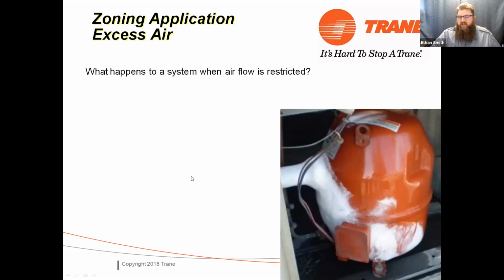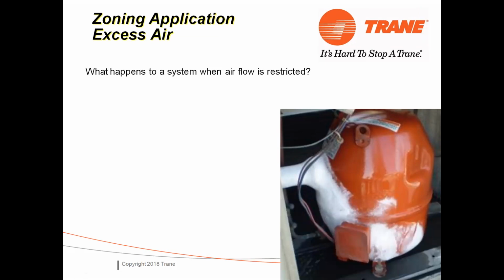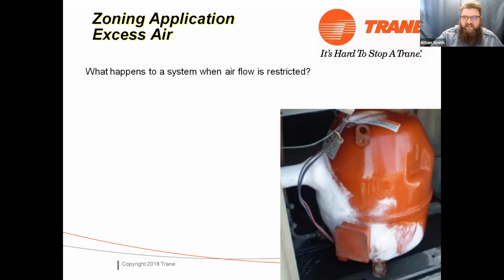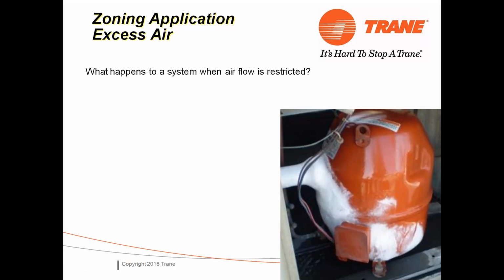I mentioned that zoning lives or dies by excess air. So what happens to our traditional systems when we restrict airflow, guys? There's a hint on the screen there for you. Freezes up. Freezes up if it's an AC. If it's a heat pump, it'll go out on high head. If it's a furnace, what happens? Goes off on high limit. Goes off on high limit, okay?